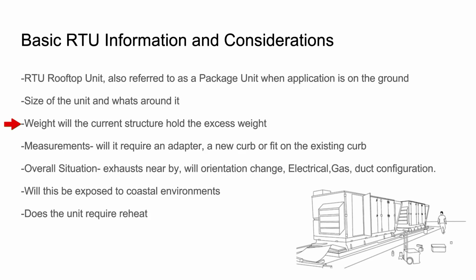And obviously, if it's new, you're looking at then what now as your ducts drop into the building, what's going to be beneath that, to make sure you aren't adding expense. If you can just drop a duct right in it, that's relatively inexpensive. If you're having to relocate electrical or relocate fire sprinkler lines, you're now looking at a huge added expense. Or if you take that into consideration ahead of time, even if you have to jog ductwork a few feet after you come in, that's much less expensive than relocating an existing utility of some kind. Of course, the weight of the current unit, if you are putting it on a roof, you need to make sure that the structure can hold the weight.